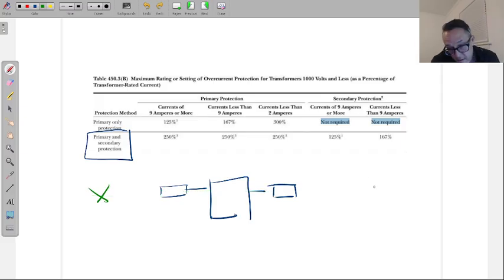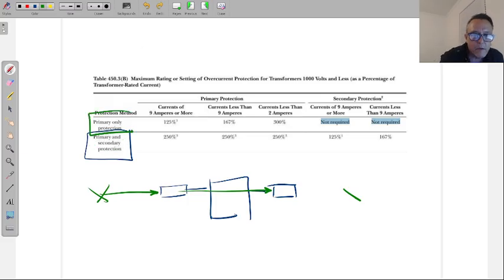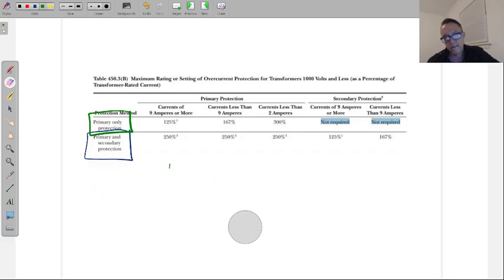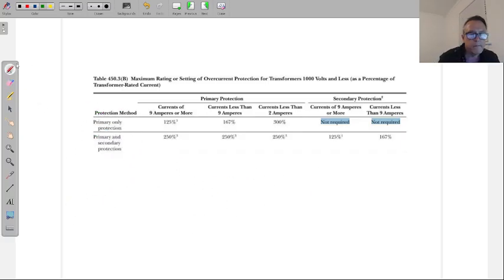Much less of a concern, but also then we have a fuse protecting from that. But a 12 volt short circuit affecting the higher voltage side, not much of a concern. But now you have this fuse to deal with the short circuit, and if anything happens, you also have a secondary fuse as well. So you can have both fuses, but again, they really want the first. This is the most important one, the one on the primary side. That's the high voltage side. That'll be the bigger fuse dealing with anything on that side, protecting it from getting into the low voltage side.